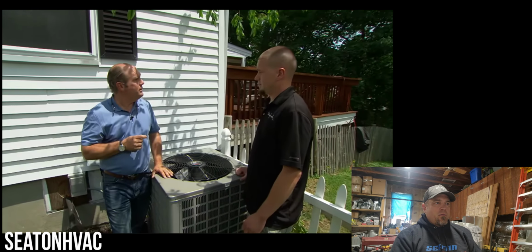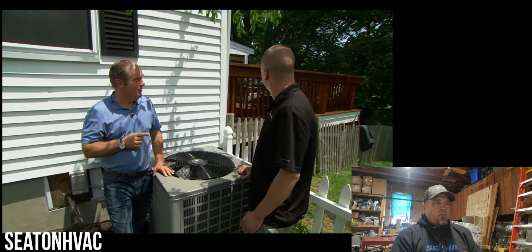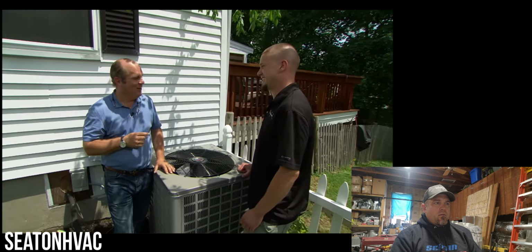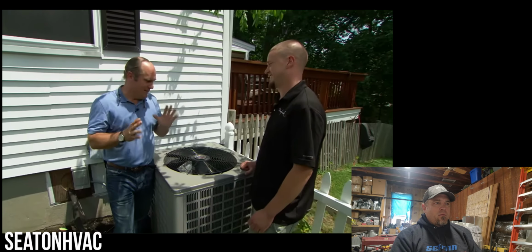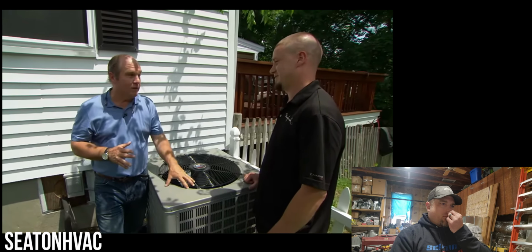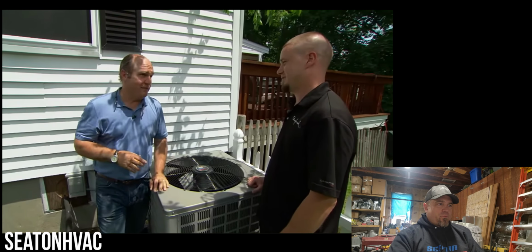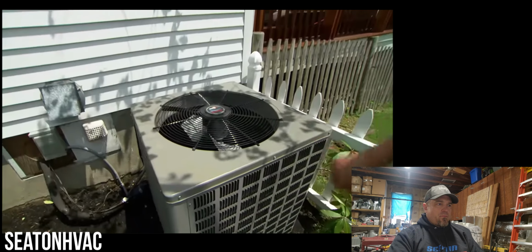Oversizing is one of the biggest issues in air conditioning because if you're too big, it just doesn't work. It'll freeze up like yours did. We want to make sure the size of this unit is just right for the hottest day of the year and no more. And in this case, we're way too big. Well, now what should we do? Well, we can put an addition on it, about a 1,500 square foot addition on the back. I think the wife would like that. We've got to think about what we can do today. And I think today what we're going to do is make this equipment go away and put the right size stuff in. And that's a pretty big job.